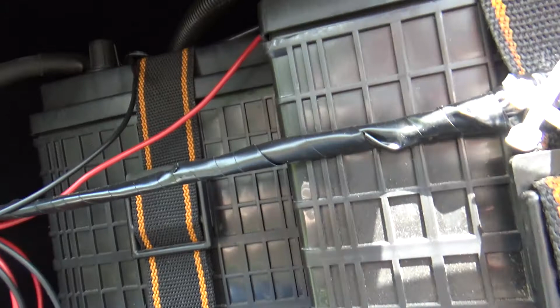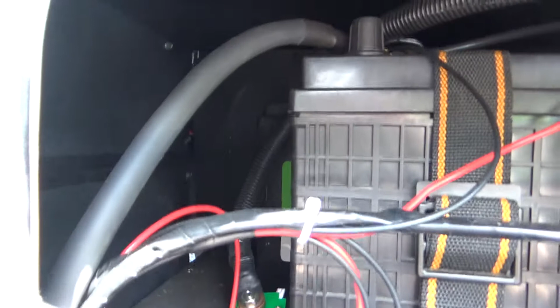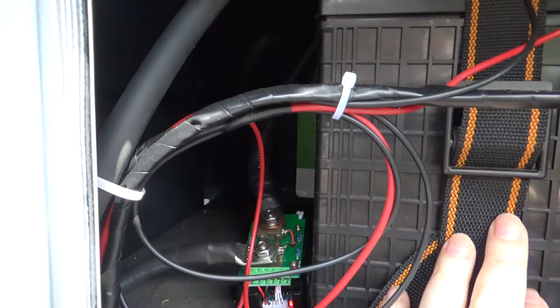It's got 4 6-volt batteries - 1, 2, and then there's 2 back there that you can't really tell, so 3, 4. These 4 are 220-225 amp hours each. Like all lead acid, even though these are AGM, you don't want to go too far below 50%. AGM can go a little lower with 6 volts, but you really don't want to.